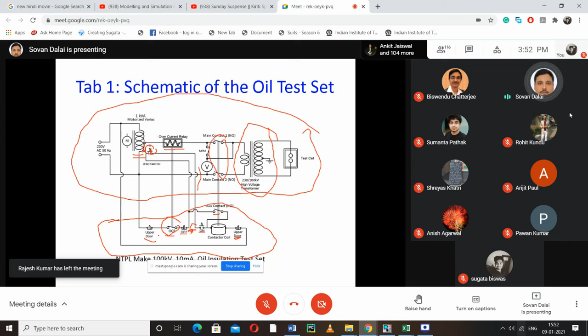So this is mainly the schematic circuit of this experiment. In that way, we can generate high voltage, and that high voltage will be applied across the test cell. Gradually you have to increase the voltage, and at a certain voltage the gap fires, and the overcurrent relay senses that short circuit current and opens this contact in the control circuit. In that way, the circuit will be de-energized, or tripping occurs.